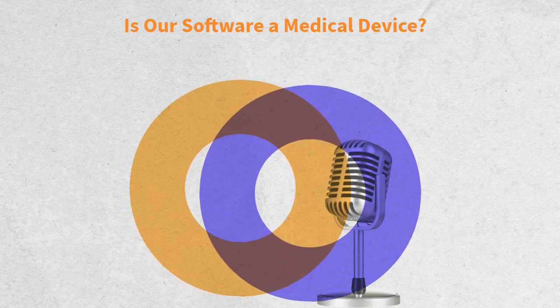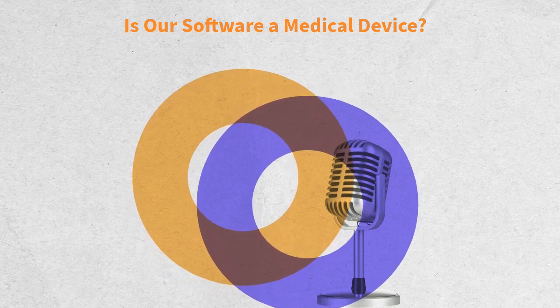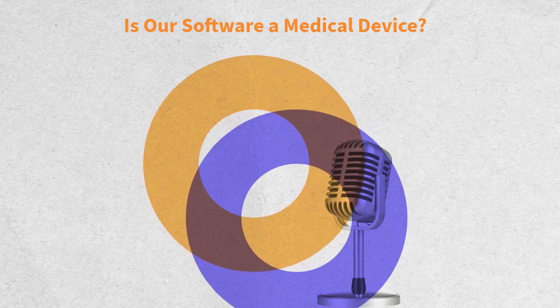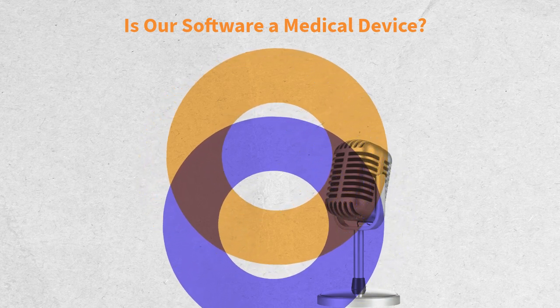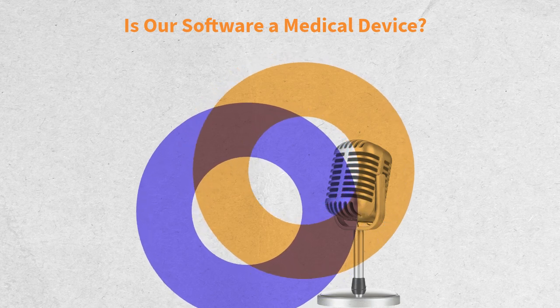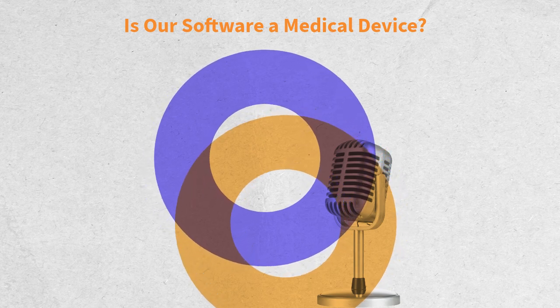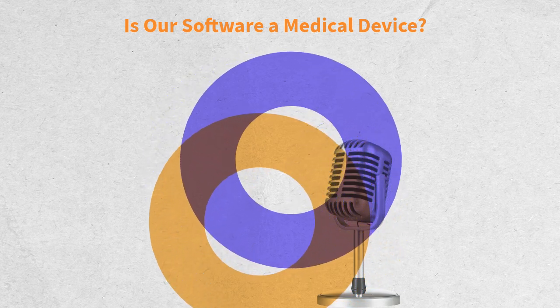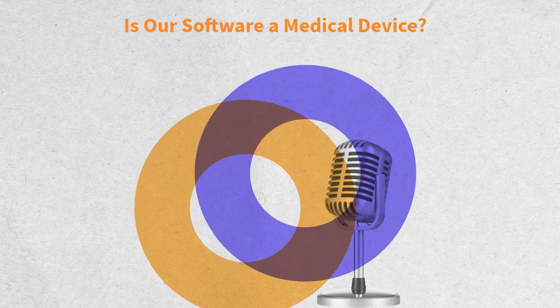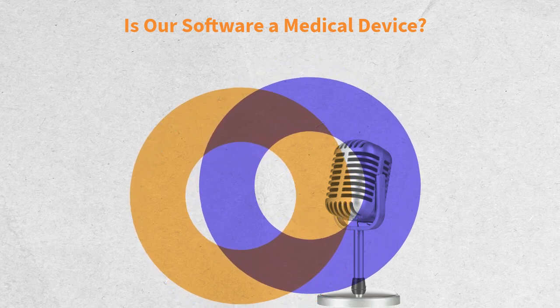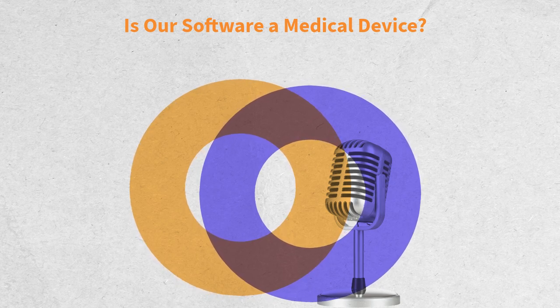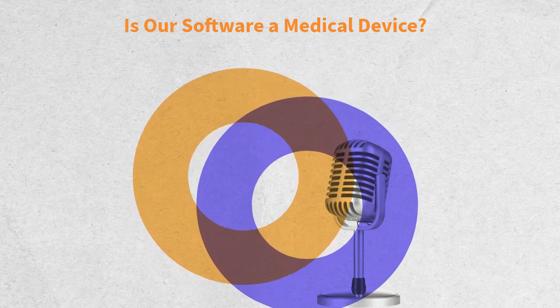With healthcare digitalization fully ongoing, many applications created for clinical or telemedicine goals are now at risk of falling into the cases regulated by Regulation EU 2017/745, the so-called MDR. But how is it possible to understand whether one's product really needs the CE marking and the associated documentation?